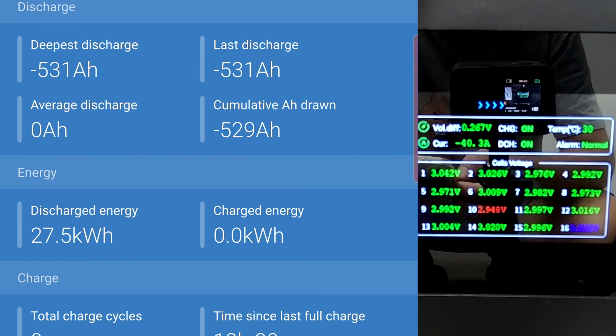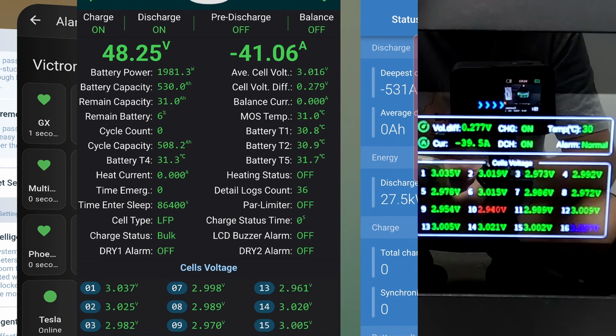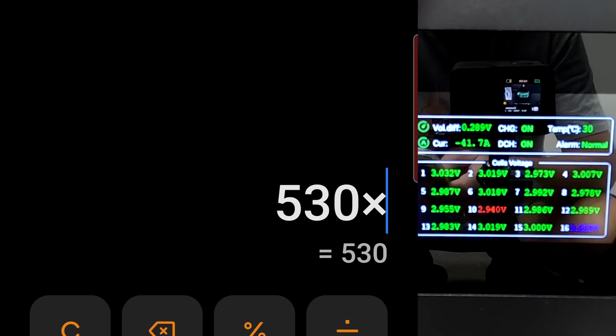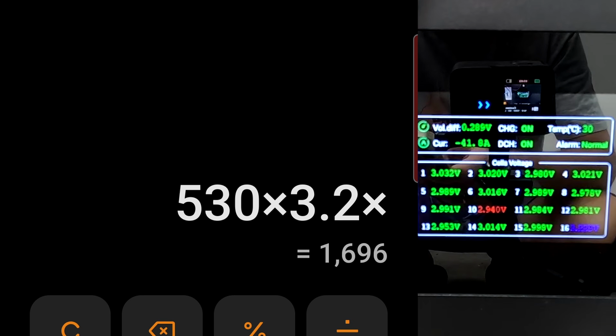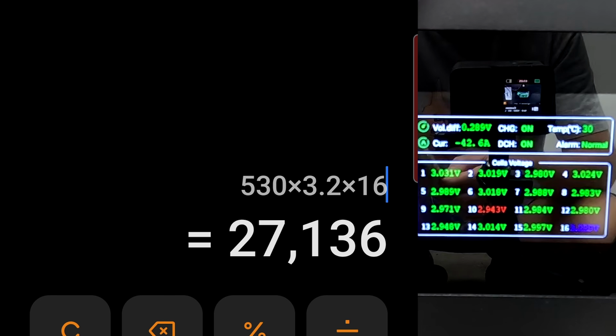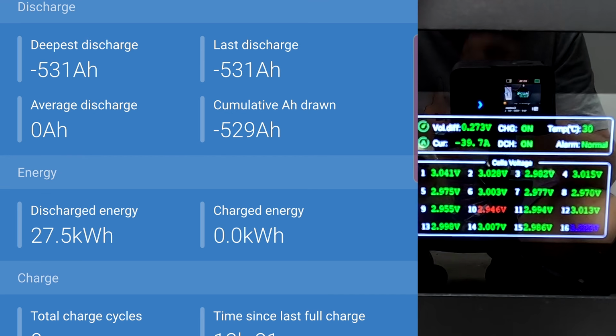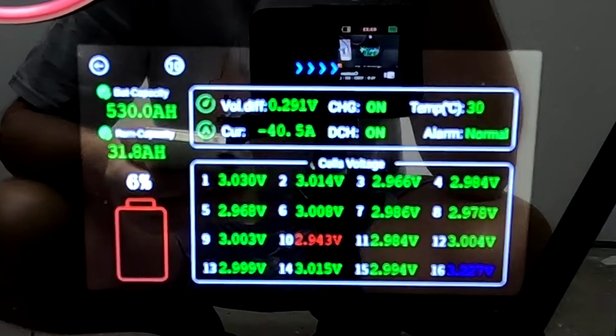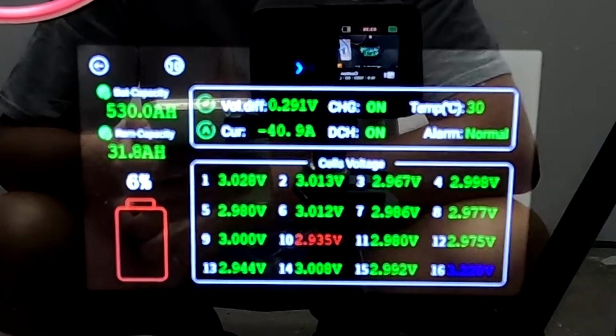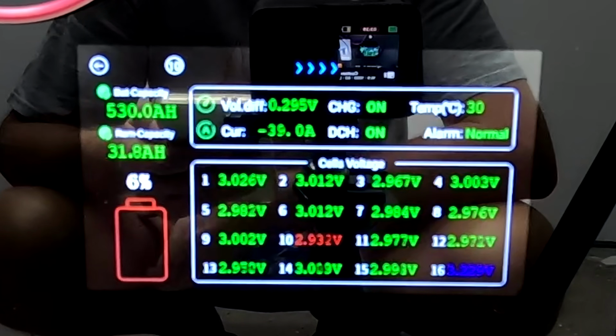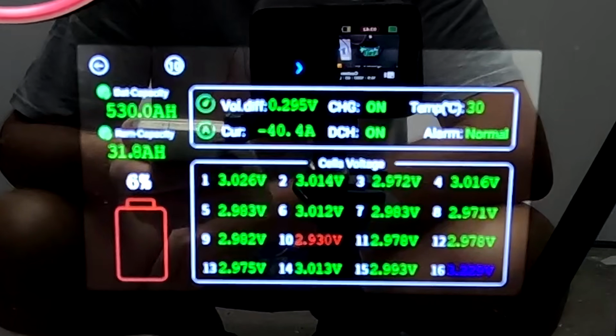Let's have a look at the history. 27.5 kilowatt hours, wow, that is also more. Hang on - 530 ampere hours times 3.2 volts per cell times 16 makes 27.13 kilowatt hours nominal energy storage, and we have already reached 27.5 kilowatt hours. So we're getting more energy delivered from this battery than it is rated for. That is always good. It may take another 10, 15 minutes or so until we see the first cell dipping under 2.6 volts, and then it gets interesting.